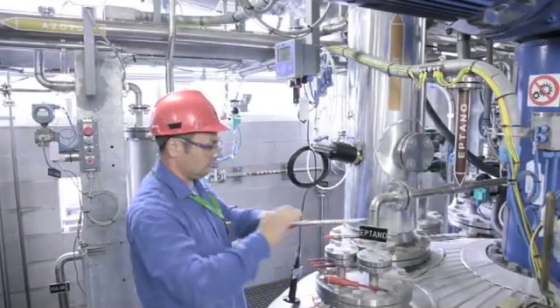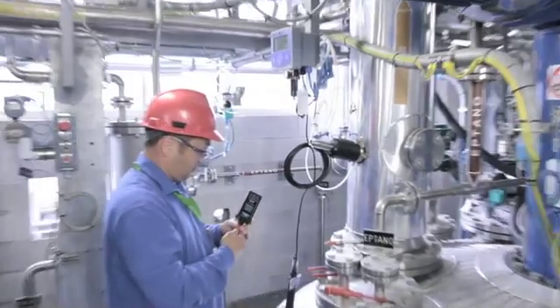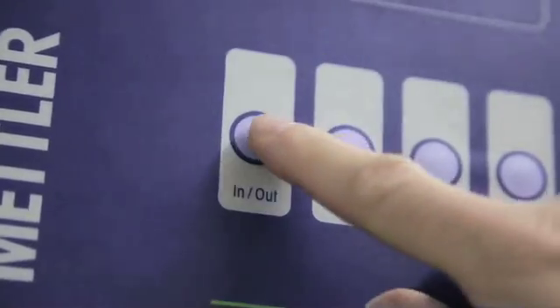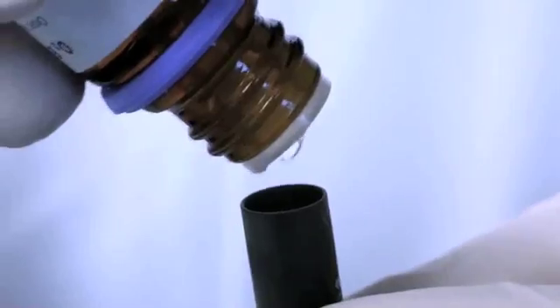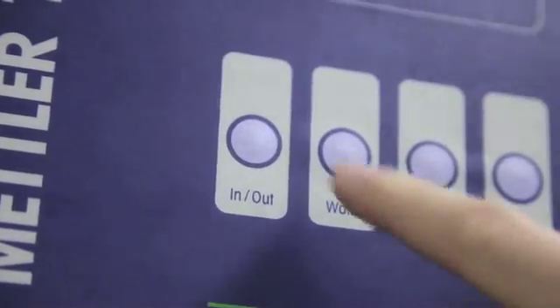One of the most compelling advantages of polarographic oxygen sensors is maintenance at the measurement point without the need for costly process interruption. Using the patented InTrac technology from Mettler Toledo, in-situ sensors are extracted safely from the process and routine maintenance tasks such as membrane replacement and sensor calibration can be performed in less than two minutes.